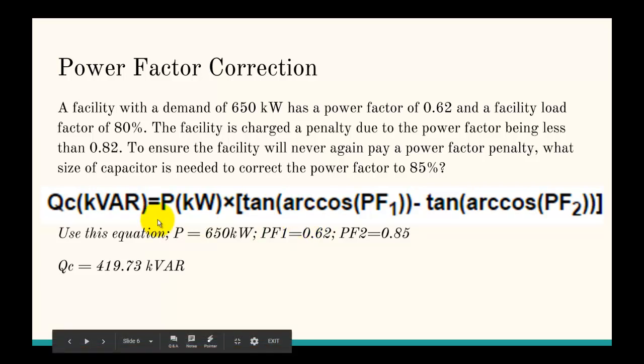Which is that the size of the capacitor in kilovars equals the power in kilowatts times this term here. Which is the tan of the arccos, or the inverse cosine of power factor one, minus the tangent of the arccos, the inverse cosine of power factor two. And, when you plug all those values from the equation, P equals 650, power factor one equals 0.62, and two equals 0.85, you get about 420 kilovars. So, that's how to do that problem.